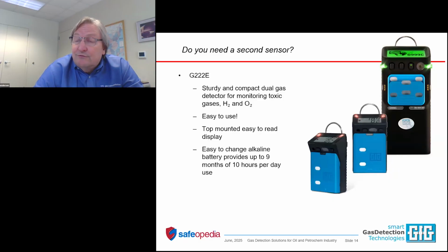Now, the H2S sensor is good for H2S. It's not good for other types of hazards. If you have a second hazard that's present, for instance, if you're manufacturing mercaptans, you might need a two sensor instrument. You don't automatically go from one sensor to 4, 5, or 6 sensors. In a lot of applications, you have two monitoring requirements. If you are doing hot work in an environment that might potentially be associated with H2S, then you certainly have SO2 as a potentially present hazard. So having an H2S and SO2 sensor in a two sensor instrument is a very nice solution. You don't always need two sensors, but when you do, they are available.